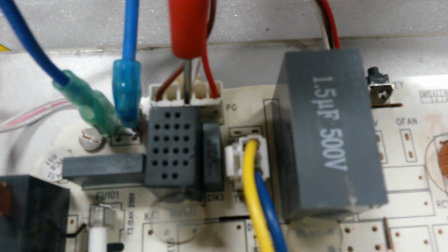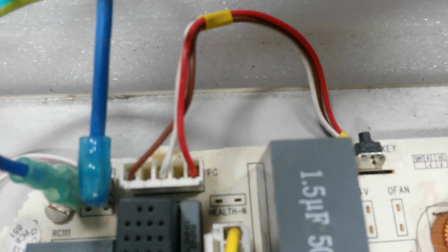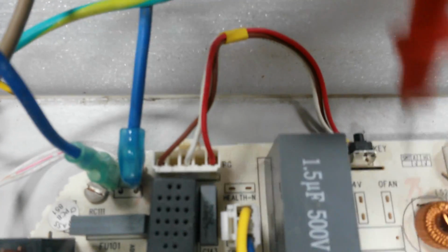So if I have to just summarize once again, phase comes here, from here it goes to my fuse, from my fuse it goes to my metal oxide varistor, from there are two connections, one goes to my blower motor, second goes to my transformer, and transformer output becomes 12 volts. So that's how 230 volts AC has converted to 12 volts AC. This 12 volts AC is then converted by this bridge rectifier into 12 volts DC.